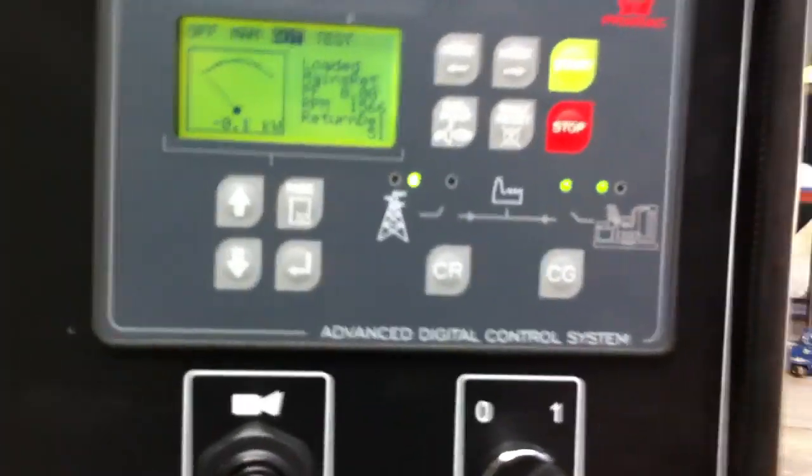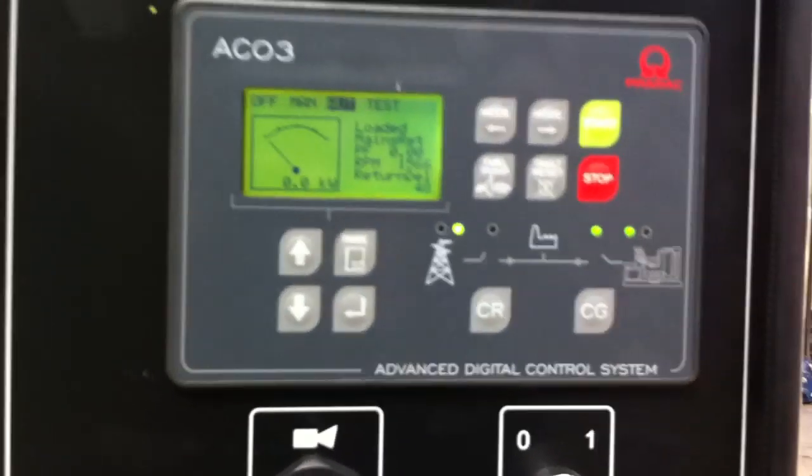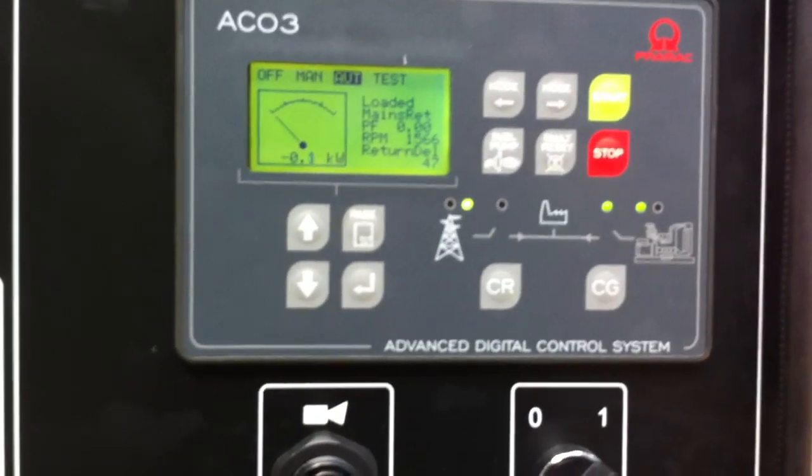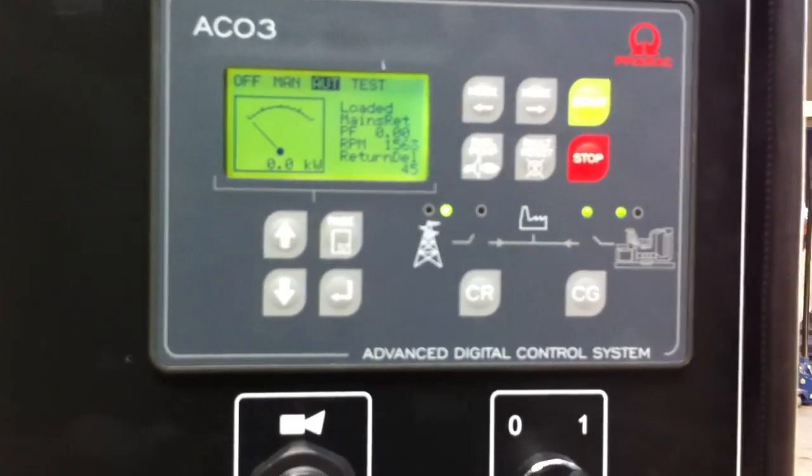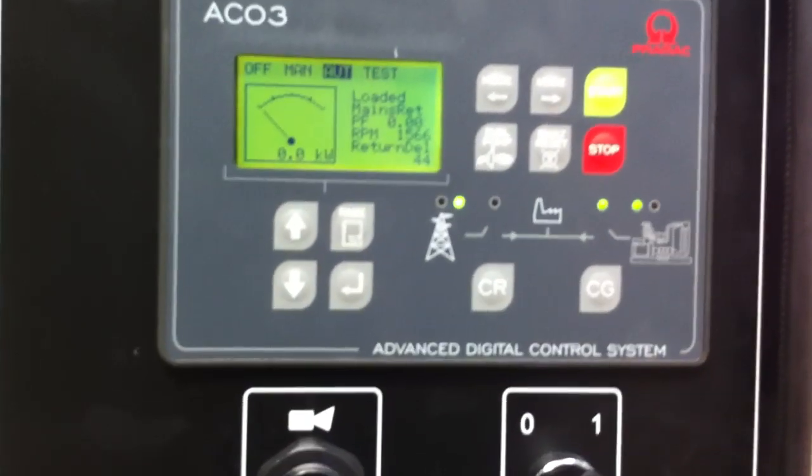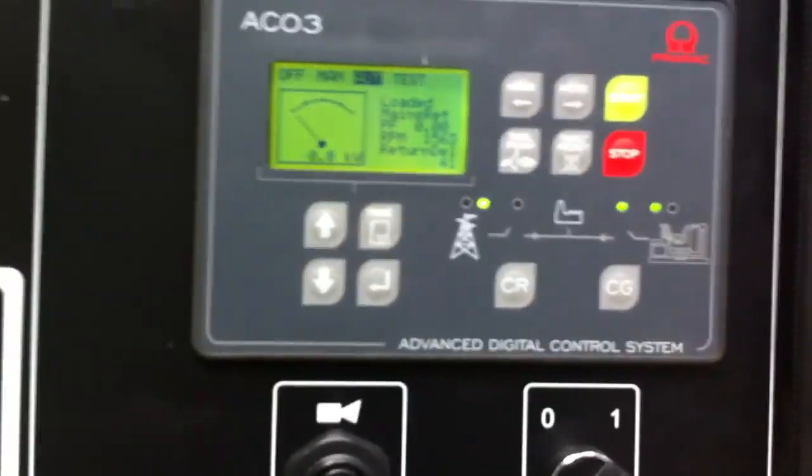Now if you look at the controller, we'll notice that it's loaded, mains has returned, and there's a return delay. There's a delay before it actually changes the contacts over.